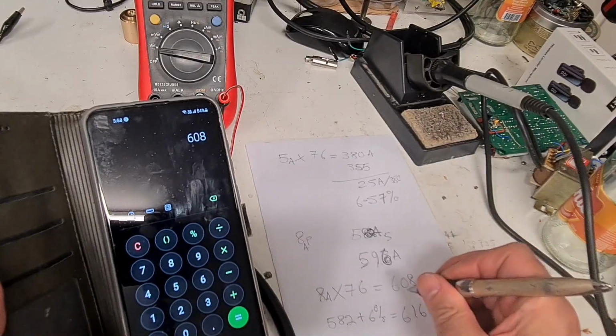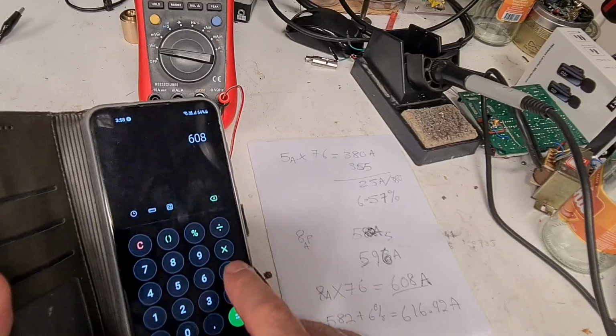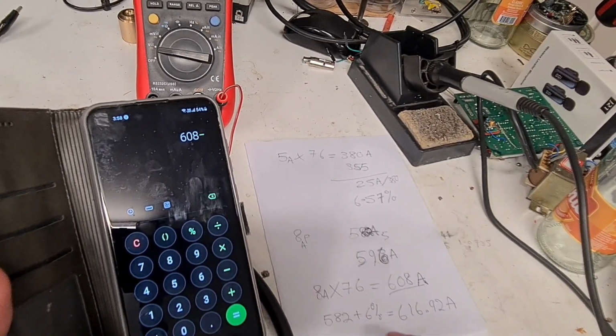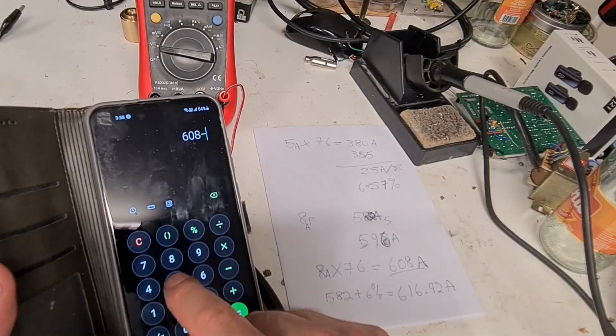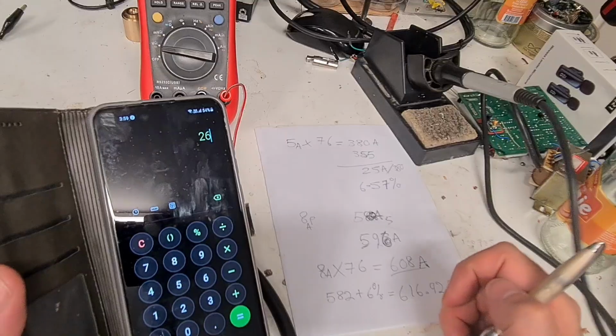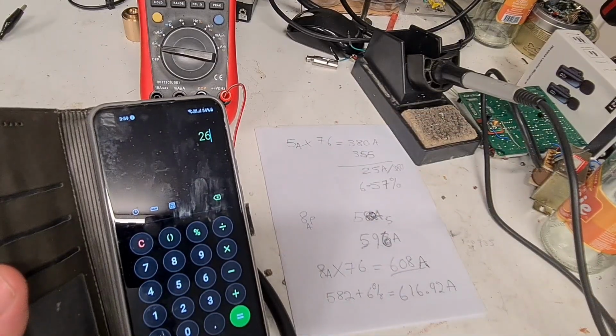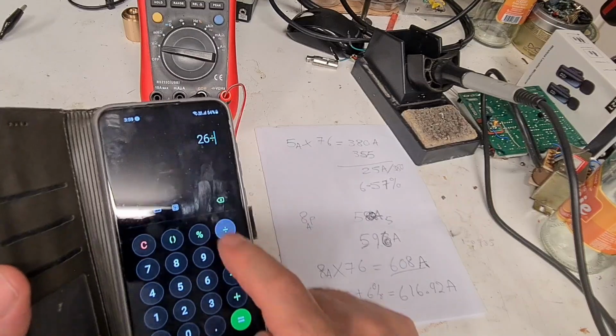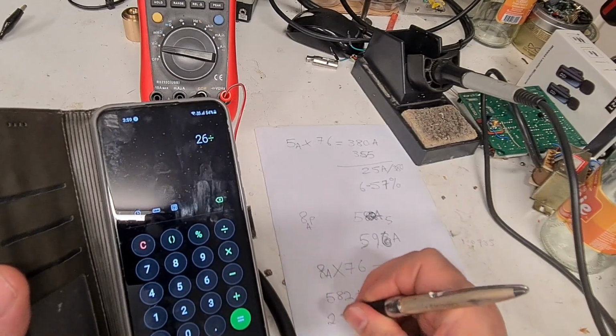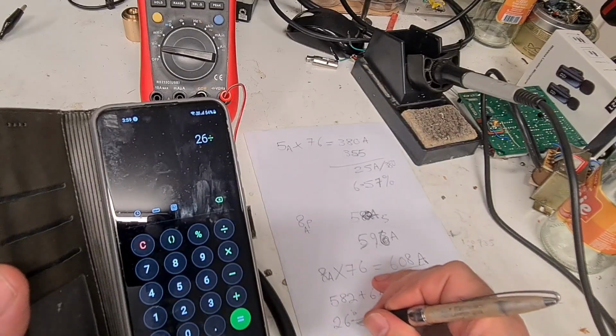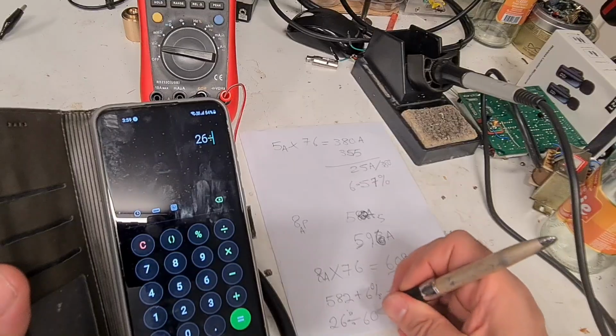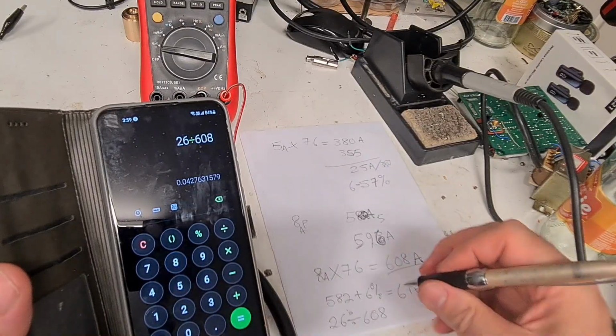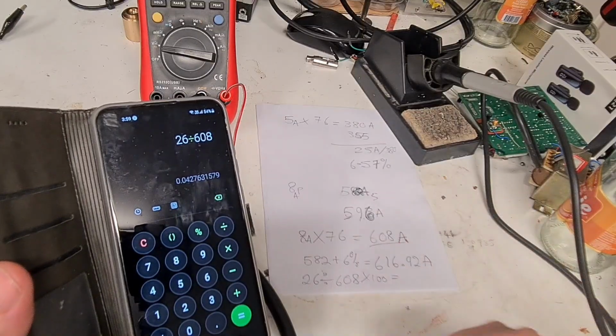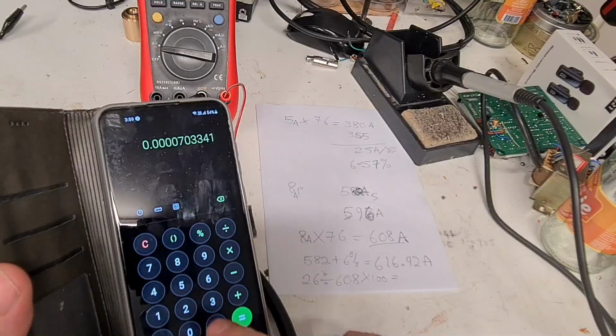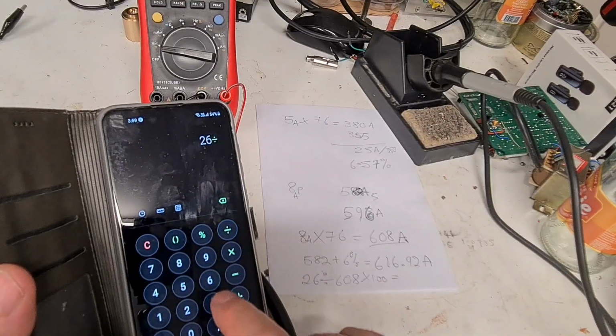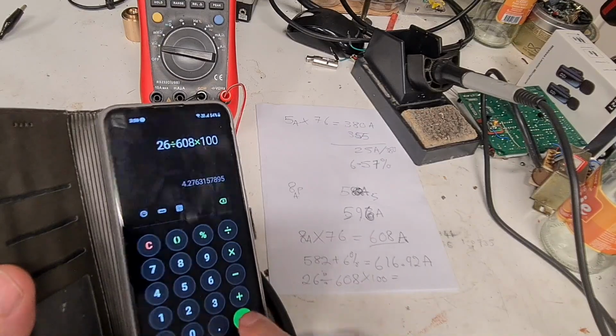608, the full efficiency of that ratio, minus what I read, 582, is 26 amps is what I lost. So, 26 amps divided by what I should have read, 608, times 100 equals the percentage. Let's do it again: 26 divided by 608 times 100.